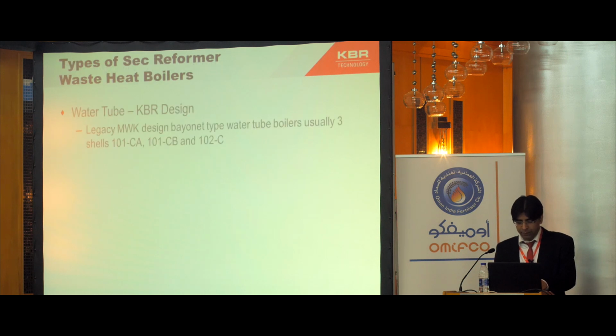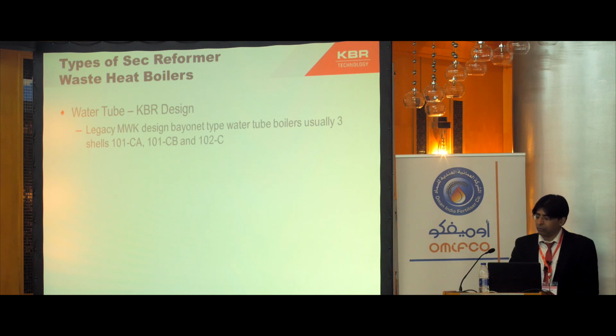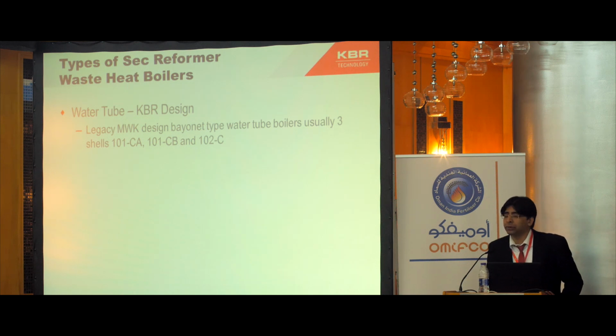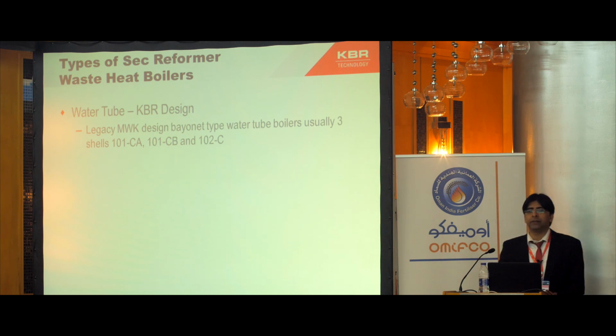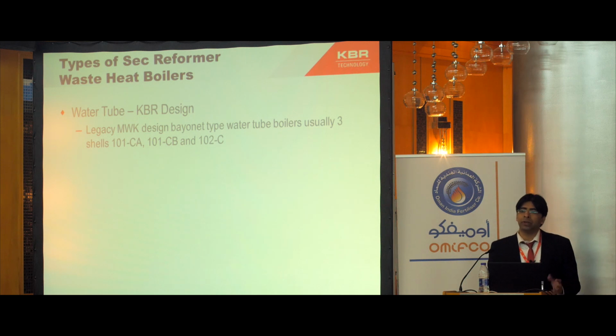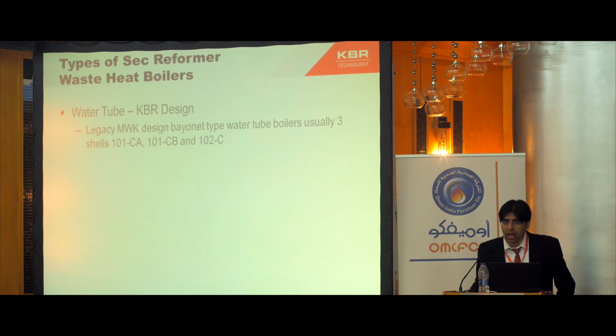So there are generally three types of waste heat boiler. First one is the KBR design, which was from very old, from before 1988. This was a legacy MWK Bayonet type design. Usually it has three shells, 101-CA, 101-CB, and 102-C. Probably if somebody has worked on an MWK plant, they will be aware of this nomenclature.